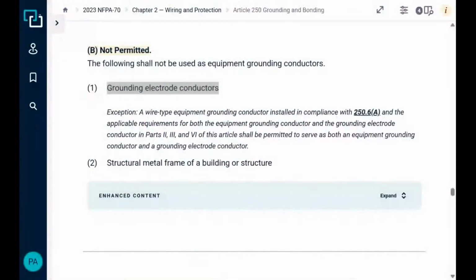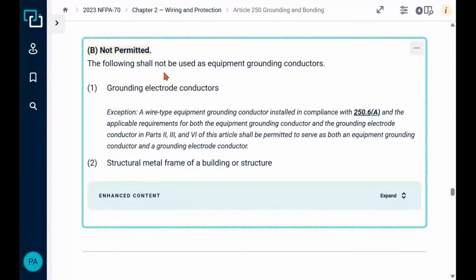Let's look right here. It says, not permitted, shall not use the EGC, okay? I cannot use the GEC as an EGC, okay? See how that sounds? So I can't take an equipment grounding conductor, I can't take a grounding electrode conductor itself and use it as an EGC. But I can use the EGC potentially, okay? Like it says right here, a wire type equipment grounding conductor installed in compliance with 250.6(A) and the applicable requirements of both equipment grounding conductors and the grounding electrode conductor in these parts shall be permitted to serve as both an equipment grounding conductor and a grounding electrode conductor, okay? They're only talking about the EGC, okay? Can serve as both.